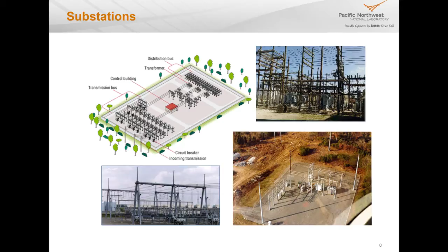Now I mentioned substations earlier. Substations are the point of demarcation between transmission and distribution, but they're also incredibly important because this is where the system is actually controlled. That control room picture I showed earlier - they have telemetry coming from the substations, monitoring the status of the system. This is where the protective relays are located, the circuit breakers, so if there's a problem or fault on a line, this is where all the equipment is that isolates that line, de-energizes it, and keeps things from becoming damaged. The substations also provide the nodes of that interconnected mesh transmission network, so substations are really important.